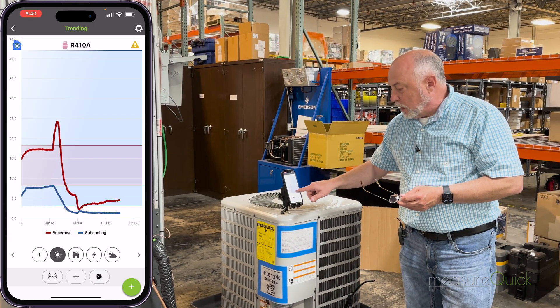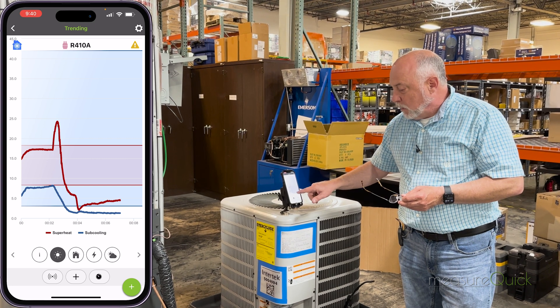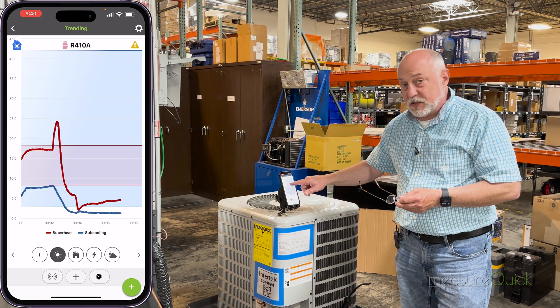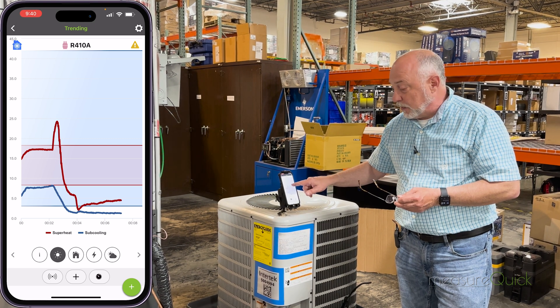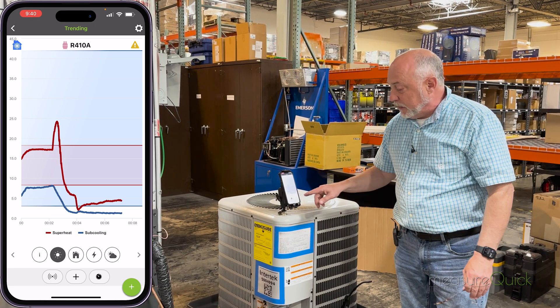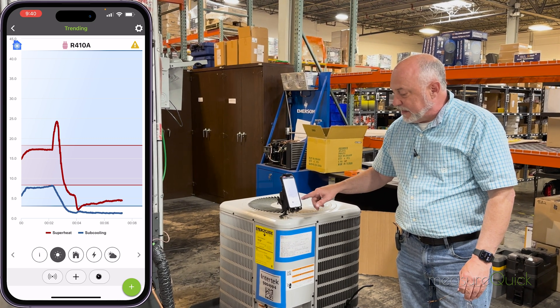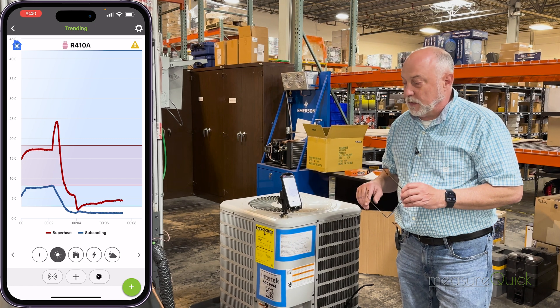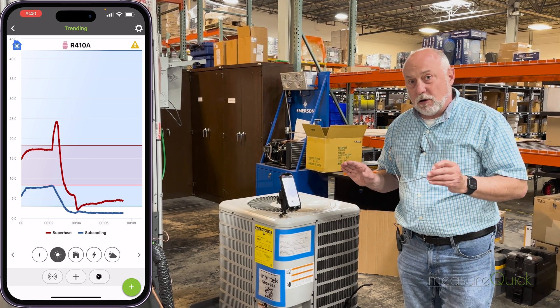Our system is pretty well stabilized out. We understand now why we had that sharp increase of superheat initially — it was due to our saturation temperature dropping faster than our suction line temperature could follow. Superheat is trending up slightly, subcooling is trending down slightly, but they're very minute. Everything is sort of where it's at. Now I'm going to put the blower door back on the unit.